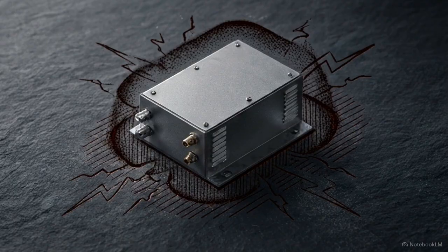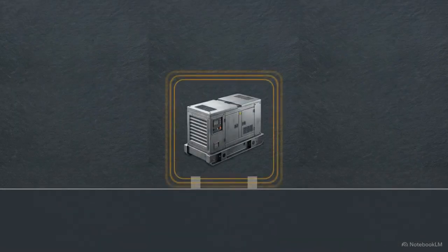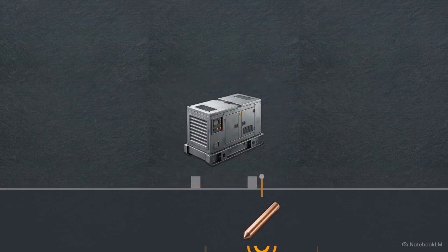During normal operations, isolated electrical systems accumulate passive energy hazards if they lack a continuous path to ground. First, accumulated static electricity builds as a surface charge on the equipment's metallic casing. Second, internal leaked currents escape their circuit, charging the chassis from inside. An active earthing pathway captures both static buildup and leaked currents, draining them instantly into the soil.